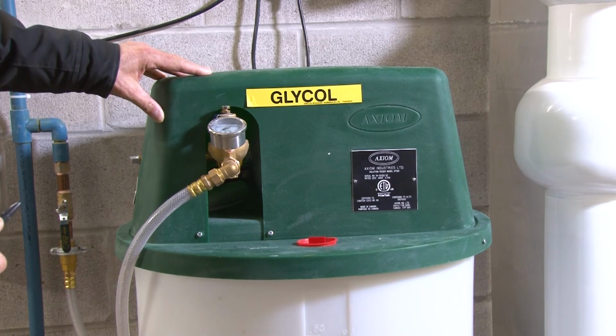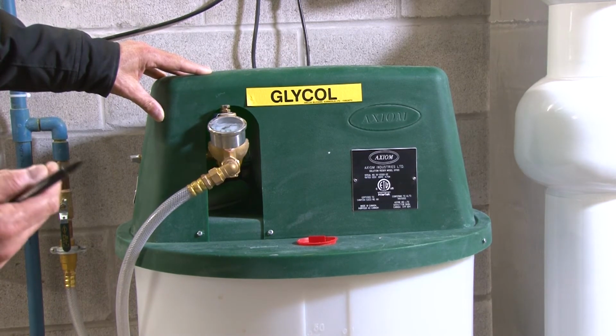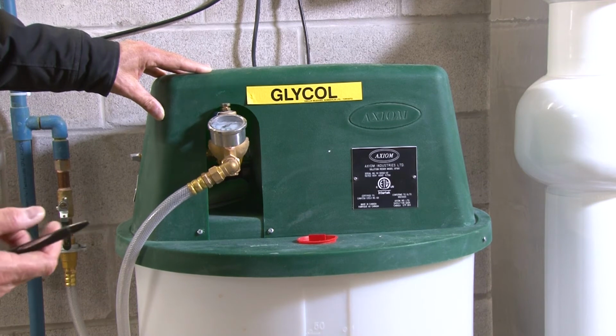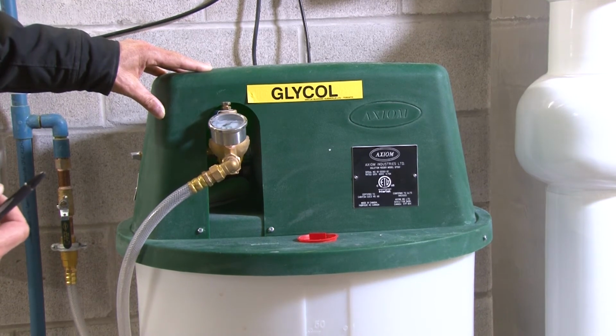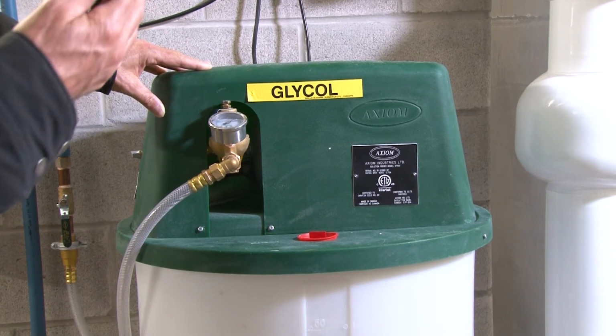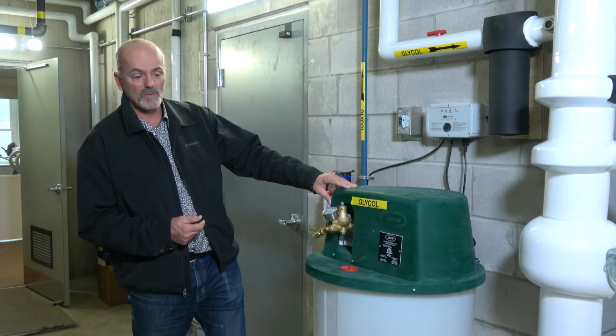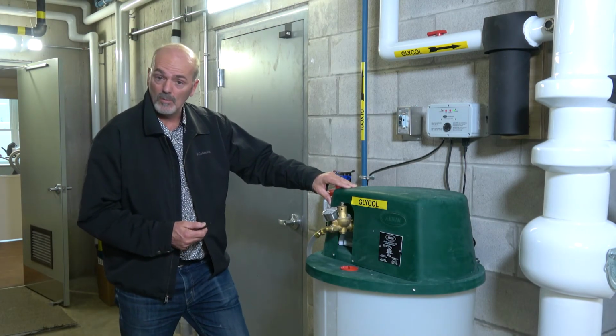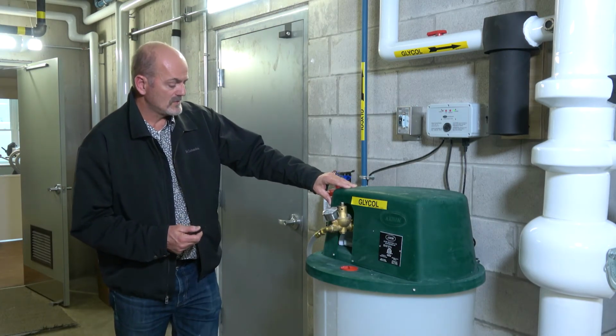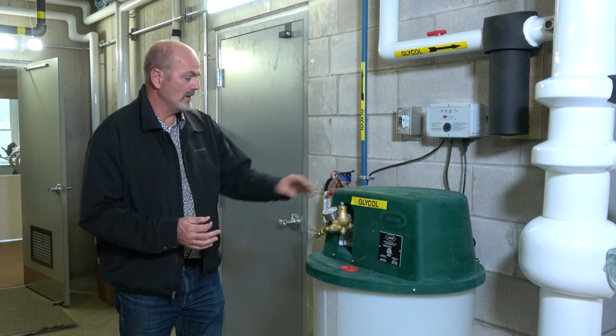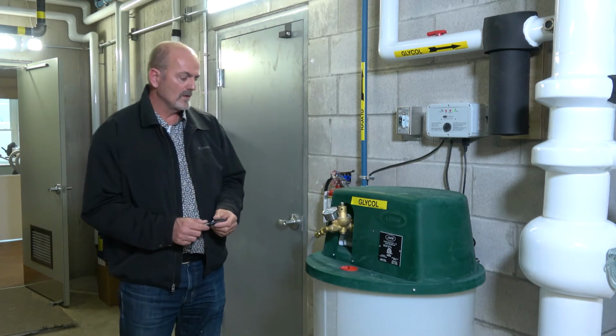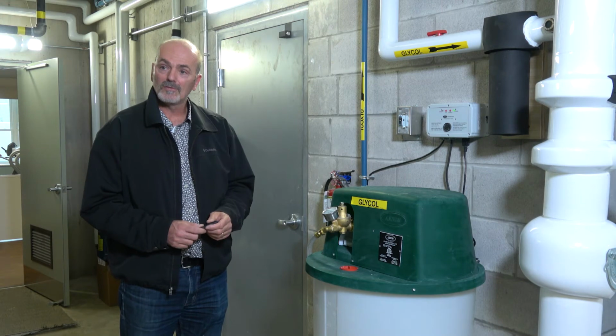You will hear it run a little bit for a few seconds or maybe a minute, for short bursts as air continues to bubble out and get removed out of the system and replaced with the premixed glycol and water. Okay? So that's about it on this. In terms of maintenance, there really isn't any maintenance.